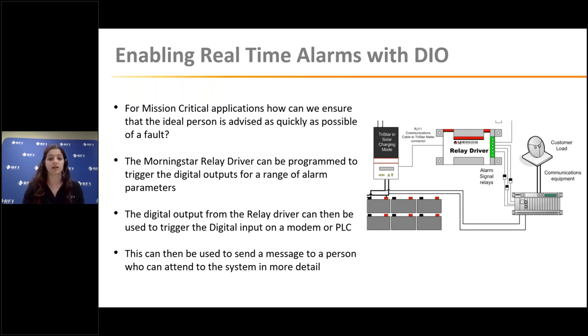One way we can do this is through the Morningstar relay driver paired with a modem or a PLC. Brad was talking about the relay driver and how it can be used for alarms as well. It's got two IO channels for alarming that can be programmed for a whole host of different aspects from the regulators - state of charge, voltage, temperature alarms, and more. That relay is just an IO circuit, so it can be used to drive an IO on something like a modem or a PLC. Then, depending on that digital input, the modem or PLC can be used to alert somebody in some way, shape, or form.